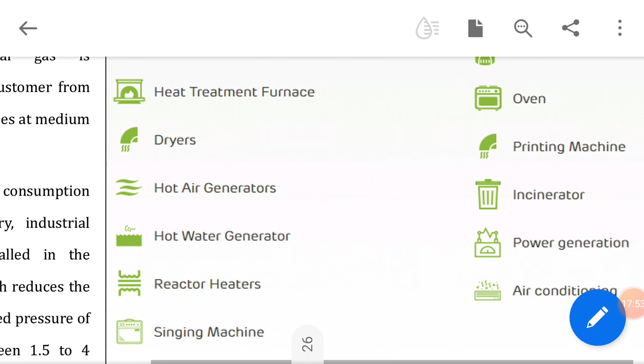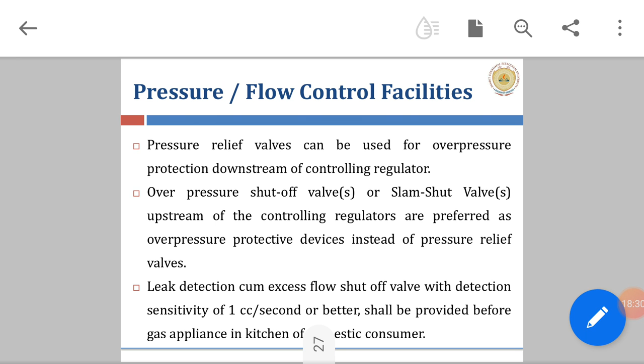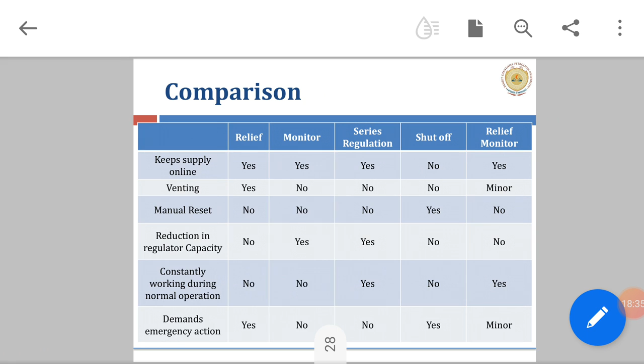A pressure relief valve can be used for overpressure protection downstream of the controlling regulator. Overpressure shut-off valves or slam shut-off valves upstream of the controlling regulator are preferred as an overpressure protection device instead of a pressure relief valve. Leak detection can come as an excess flow shut-off valve with detection sensitivity of 1 cc per second or better. It shall be provided before the gas appliance in the kitchen of the domestic consumer.